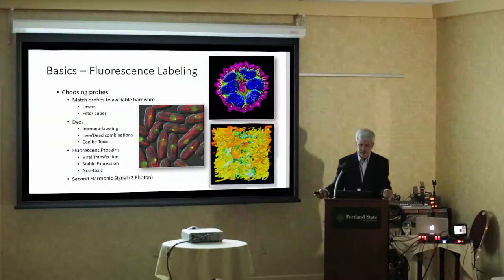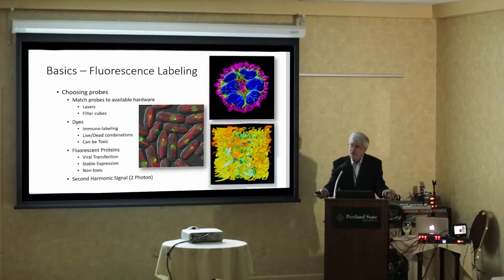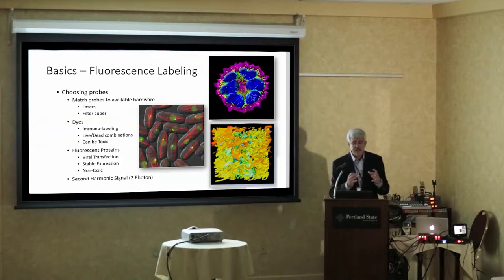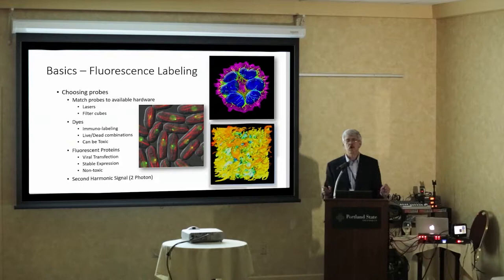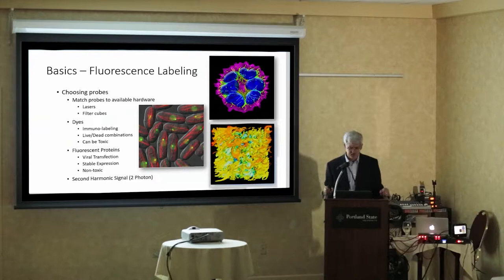Let's take a longer look at fluorescence labeling. There are issues with fluorescent labeling — you want to match your probes to the hardware you've got. Somebody comes in and says they've got cells labeled with CFP and YFP, let's use the SP8. Guess what — I can't, because I don't have a laser that will excite CFP on that particular one. I've got to use the other scope, which means another kind of dish, and another type of environmental control. It all ties together.